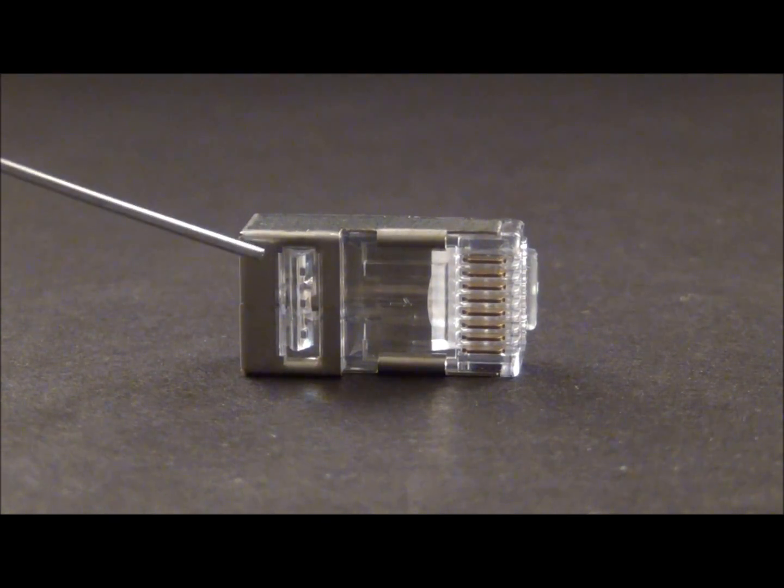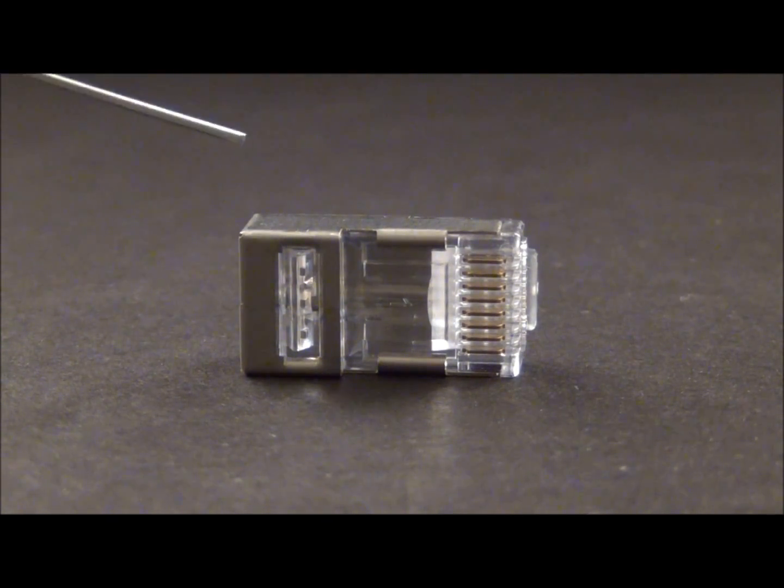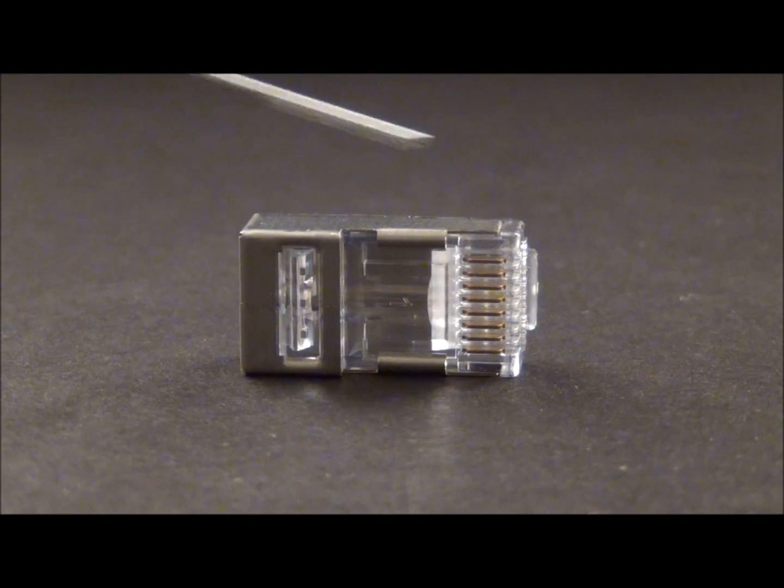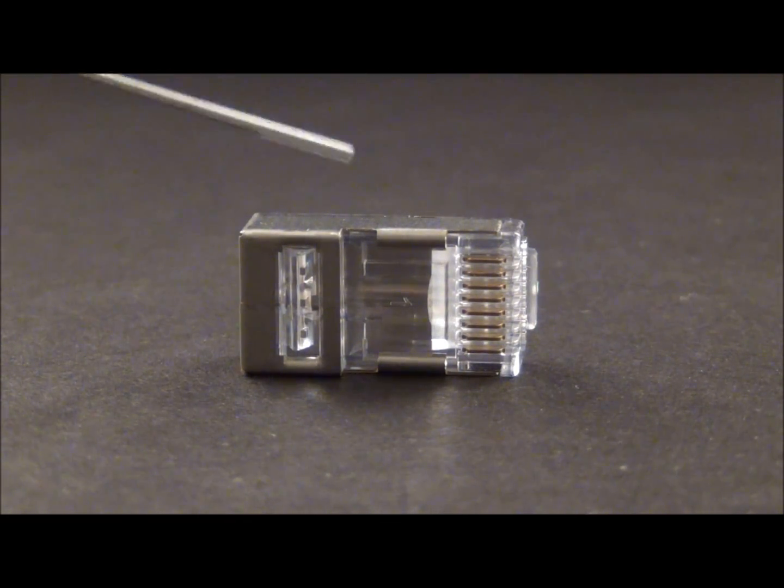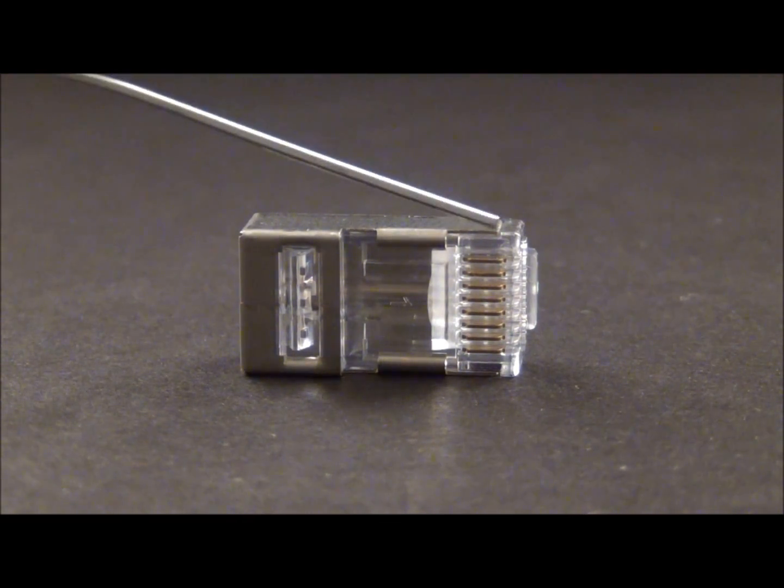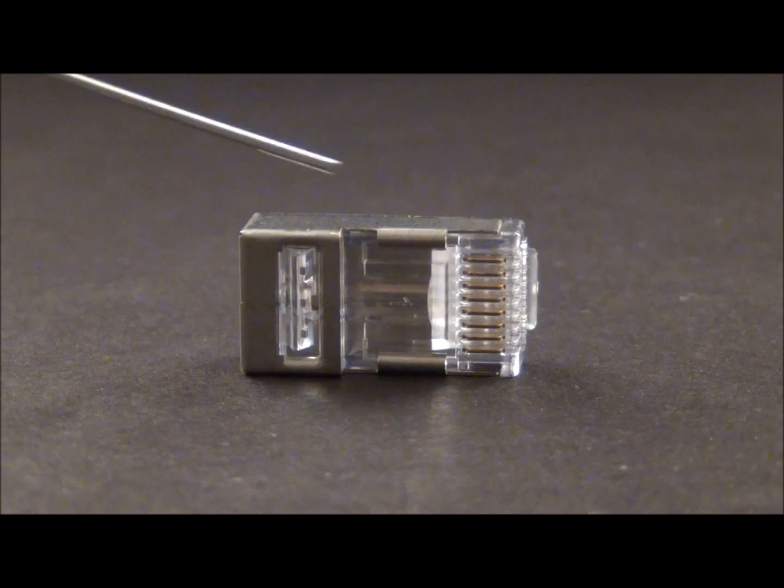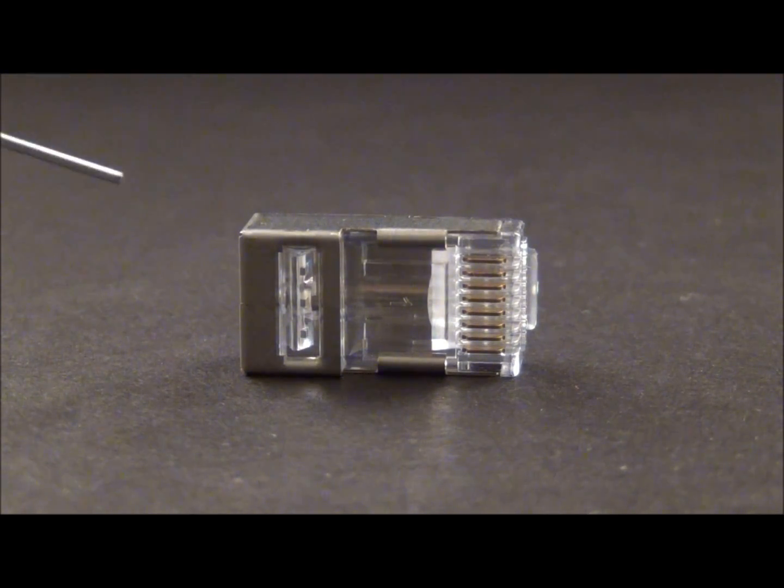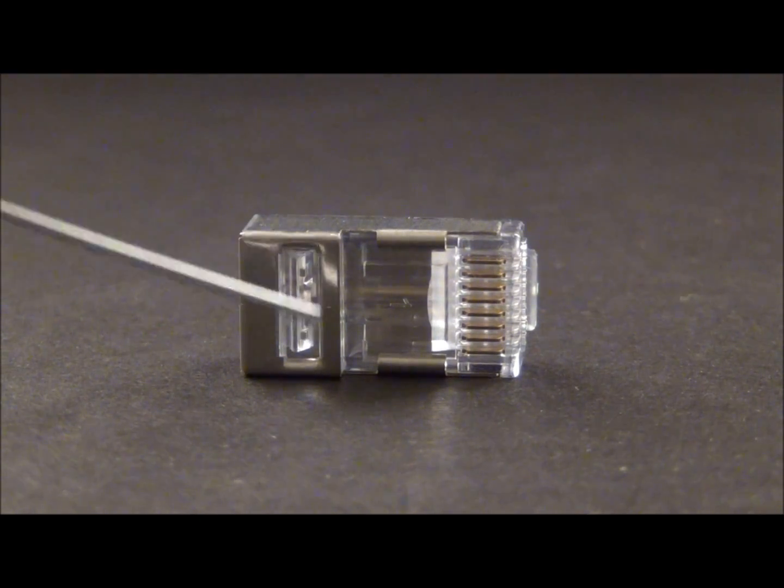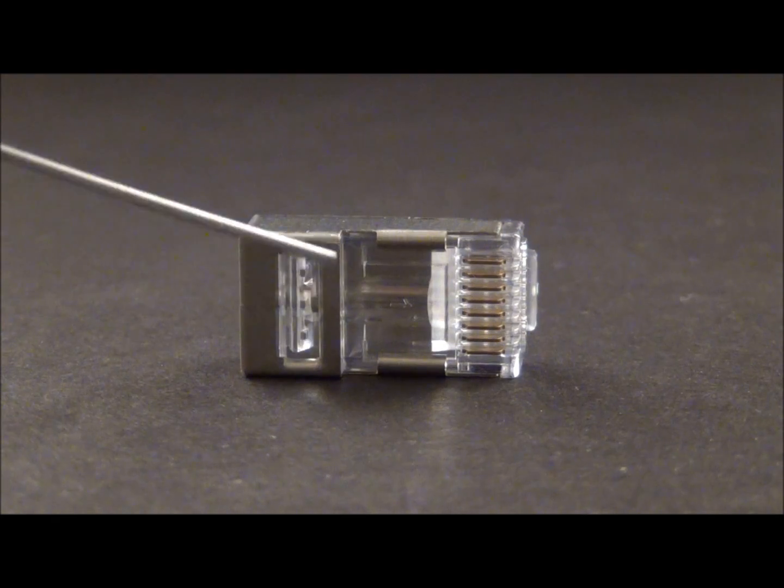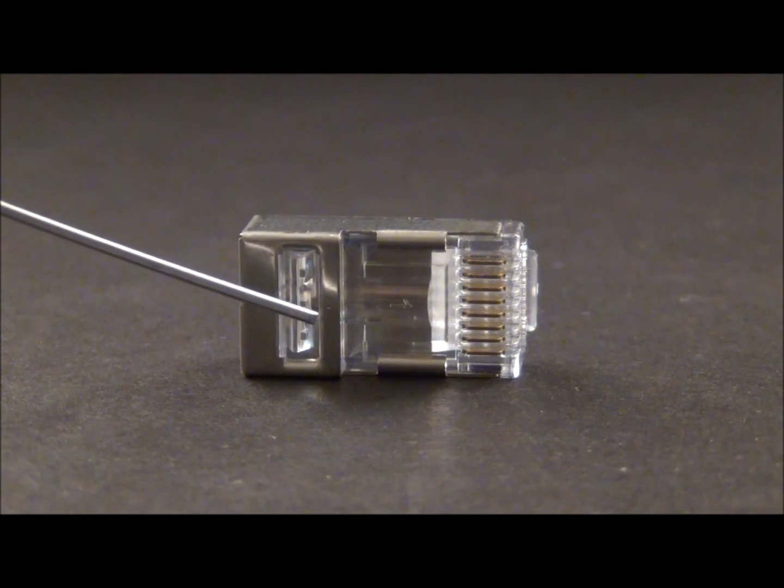And your 5E, remember the distance of the twist to the point of termination is the key. On 5E, your twists have to be less than half an inch. So that means that when you prep your cable, that jacket is going to be about right there, right past that strain latch.